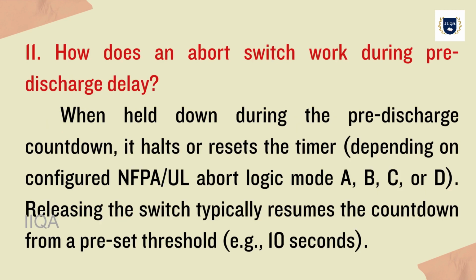11. How does an abort switch work during pre-discharge delay? When held down during the pre-discharge countdown, it halts or resets the timer depending on the configured NFPA abort logic mode A, B, C, or D. Releasing the switch typically resumes the countdown from a preset threshold, for example 10 seconds.